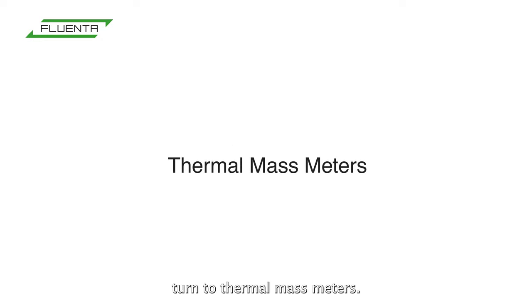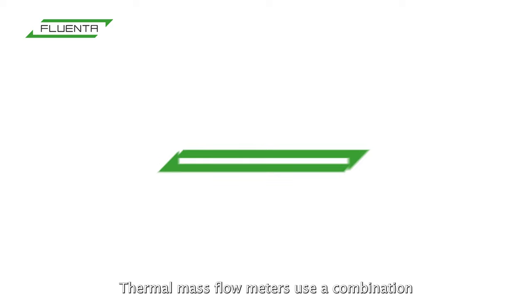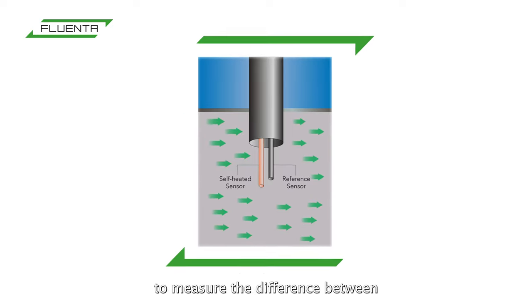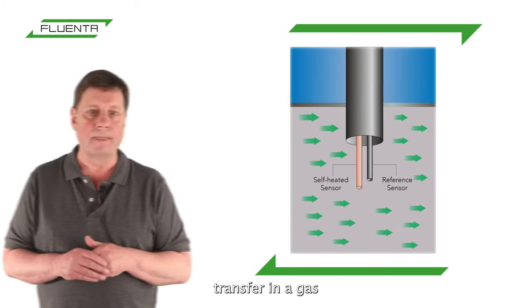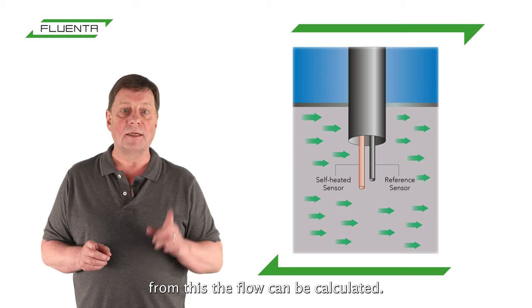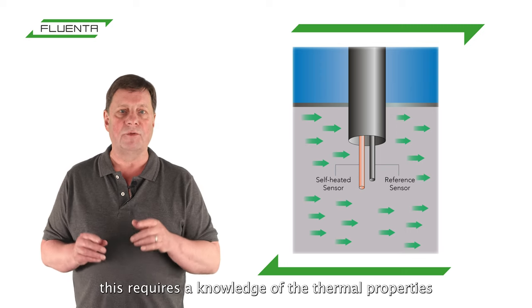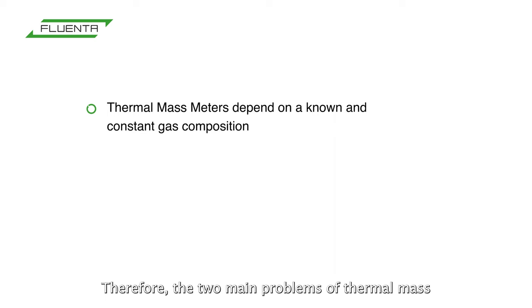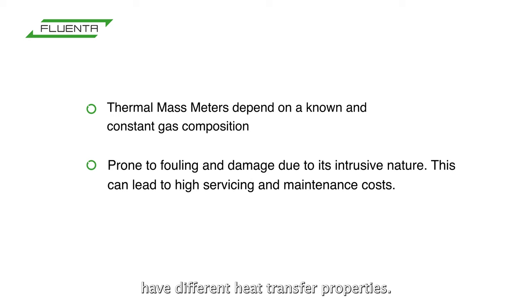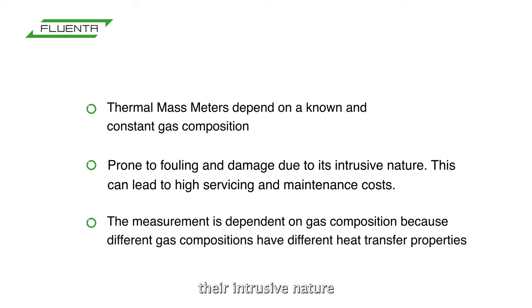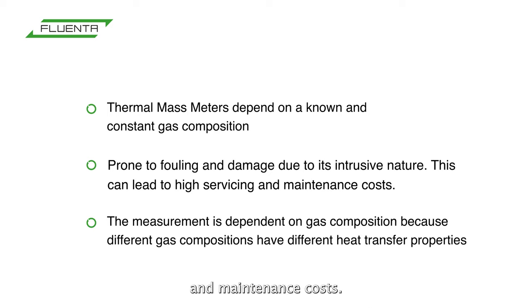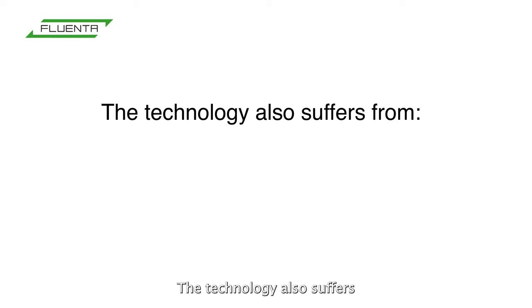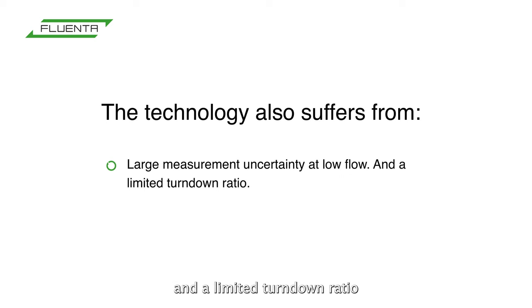Let's turn to thermal mass meters. Thermal mass flow meters use a combination of heated elements and temperature sensors to measure the difference between static and flowing heat transfer in a gas. From this, the flow can be calculated. However, this requires a knowledge of the thermal properties and density of the gas. The two main problems with thermal mass meters are: the measurement is dependent on the gas composition, because different gas compositions have different heat transfer properties; and their intrusive nature makes them vulnerable to fouling and damage, which can lead to high servicing and maintenance costs. The technology also suffers from a large measurement uncertainty at low flow and a limited turndown ratio.